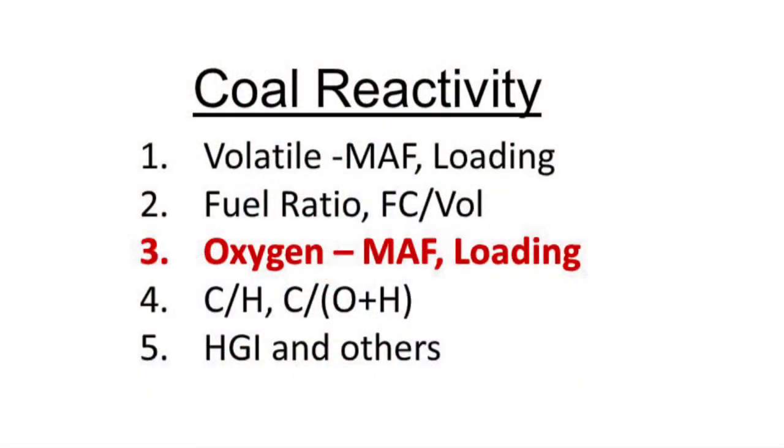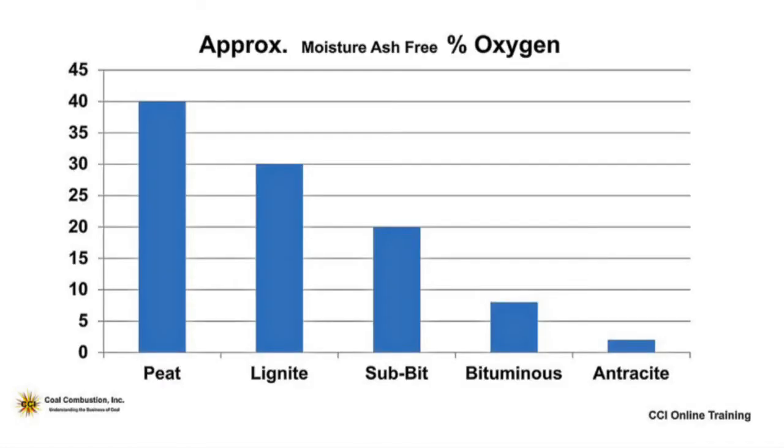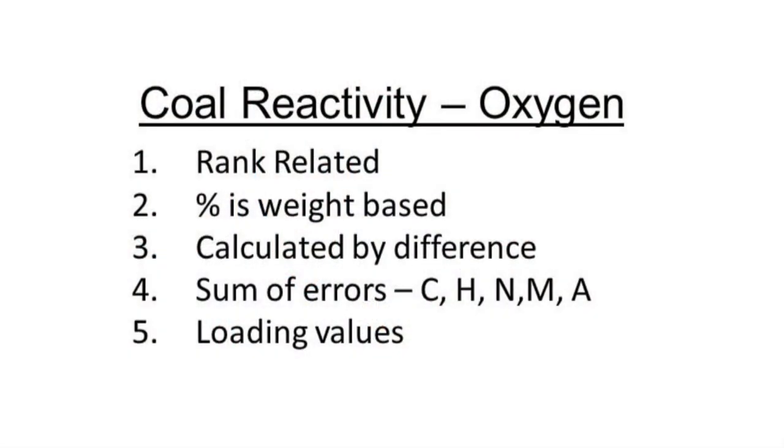Looking at the oxygen content from the ultimate analysis, we see that the original woody or plant material is very high in oxygen, then a slow decrease in oxygen from lignites to sub-bituminous. Getting down to the bituminous, they might only have about 10% oxygen. Down into the low volatile and anthracite coals, it might only be 1–2% oxygen. So we see a correlation: oxygen concentration goes down as rank goes up, and the corresponding carbon value goes up. If I look at the oxygen concentration in a coal and it's high, I'm going to think that's a more reactive coal.